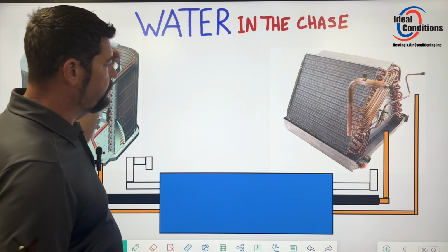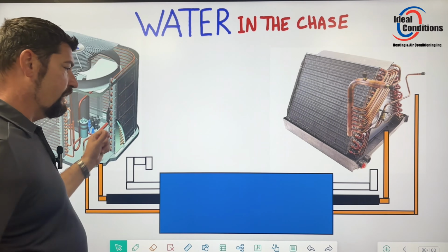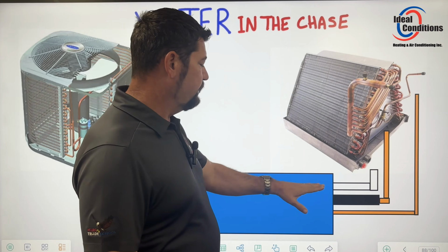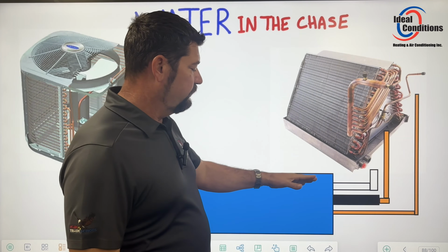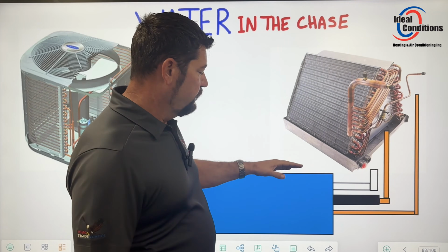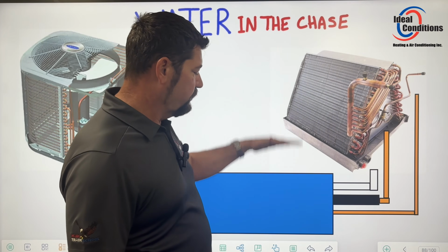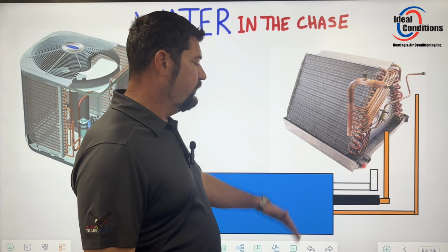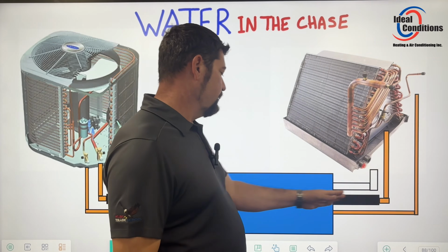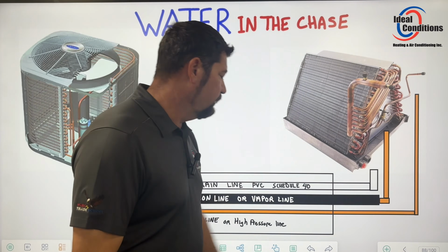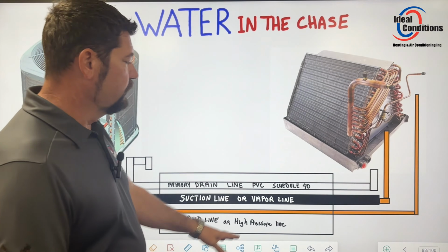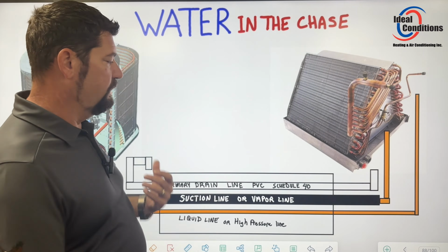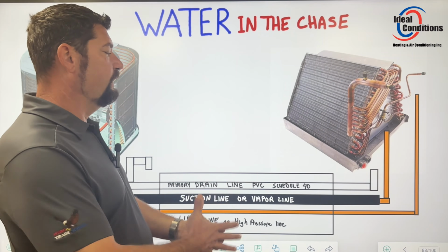Now, if you have to go up and over, I would recommend using 1/2 inch wall, just because in the chase it's not affected by sunlight. It's a cool environment. This chase is surrounded by concrete on one side and earth on the other. And so it's typically 72 degrees. That's very ideal for refrigerant lines to run through as long as the chase is empty of water, dry. But if it's going across a hot attic and down the side of a building, those temperatures are never going to stay 72 degrees.